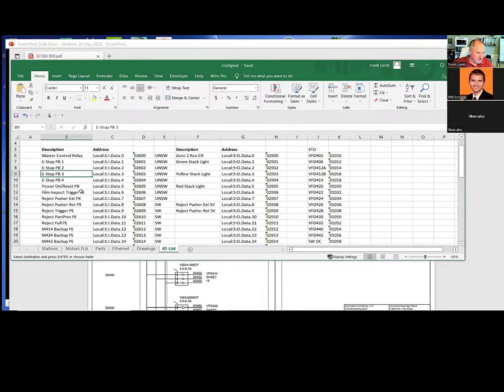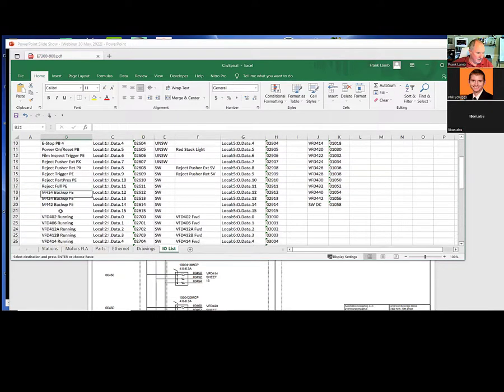This is photo eyes and proximity switches, and there's room for only one spare here. However, with Allen Bradley you can take an Ethernet connection and put remote Flex IO or Point IO up on top of the conveyors or at the far end, so I don't have to use all this as spares.